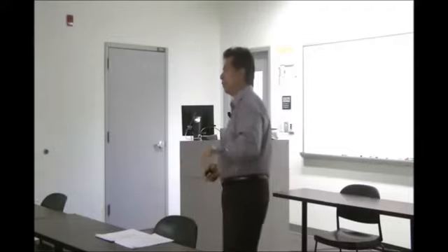When I talk about idle, the temperature is probably going to be raised if it's summertime. So if it's typically 70, 72 degrees, it will probably be raised to 78, 80 degrees. Why? Because I'm saving energy, right? Less wear and tear on my equipment. Lighting will be automatically shut down for floors I know I have nobody there, right?